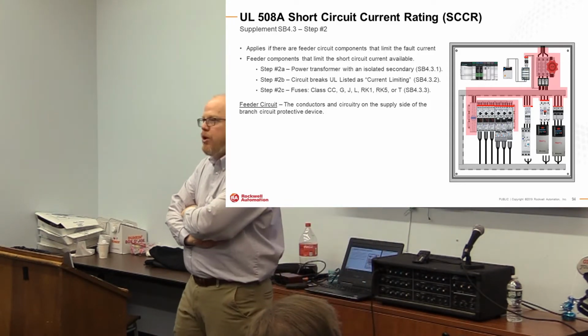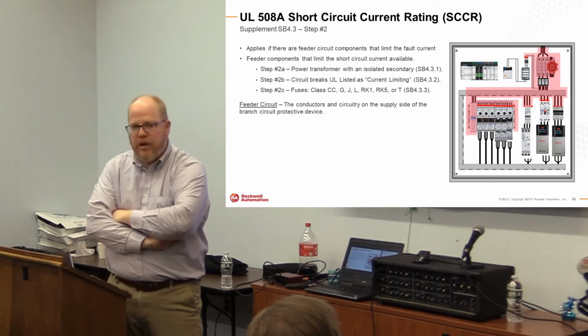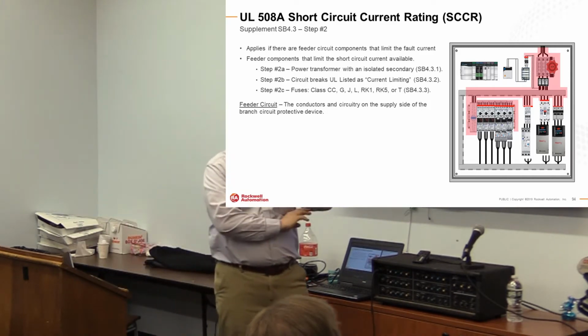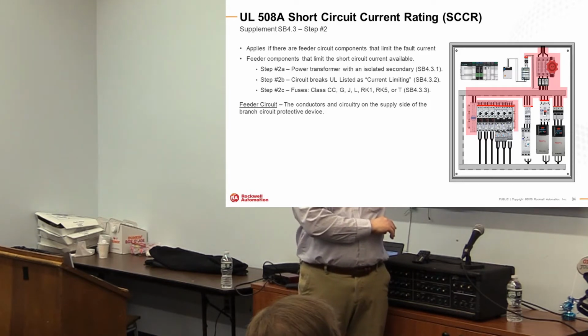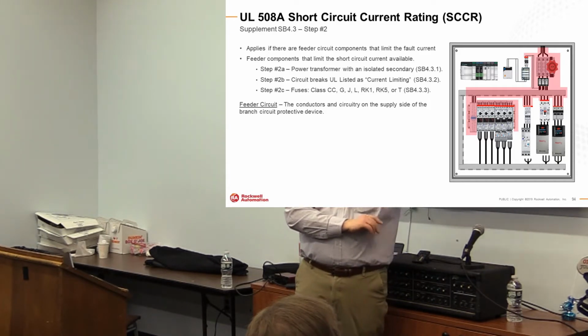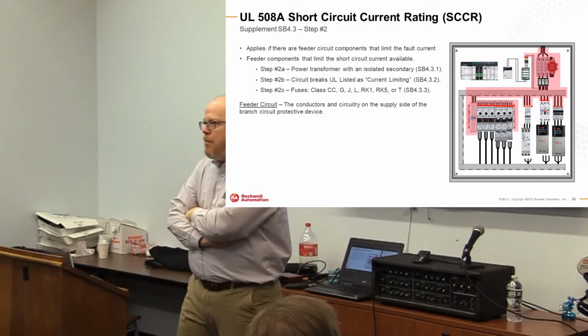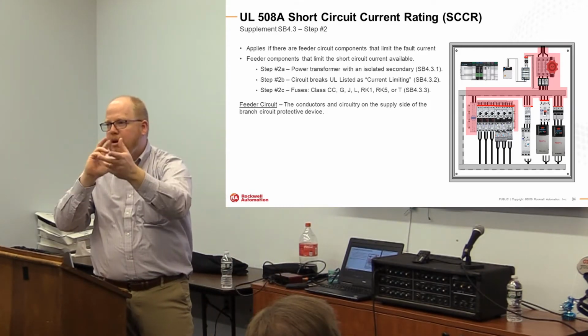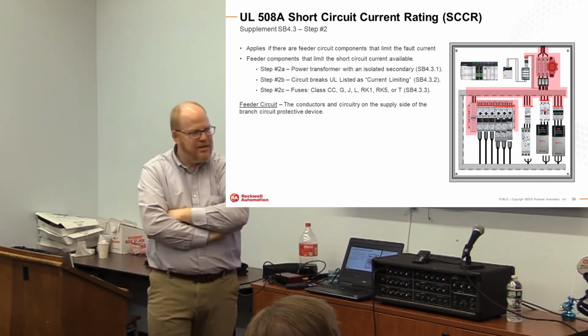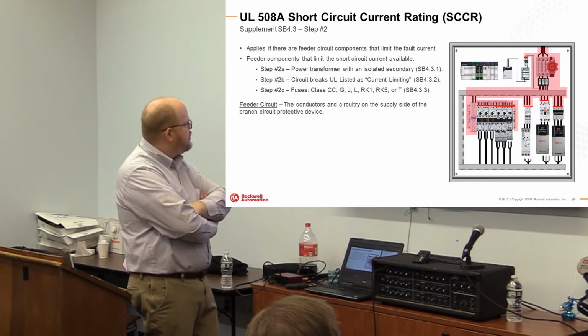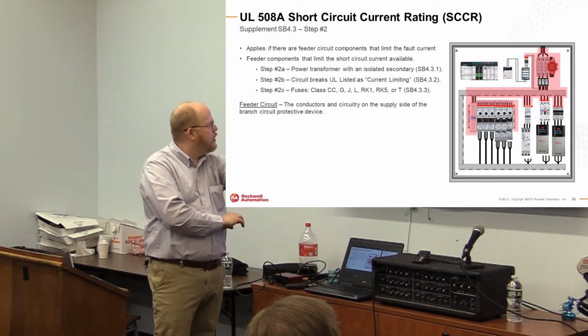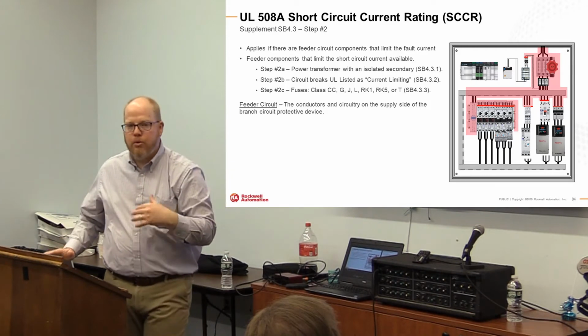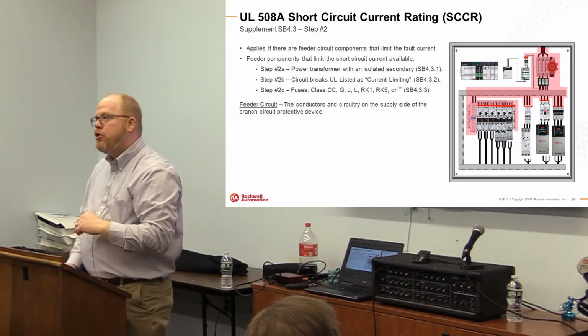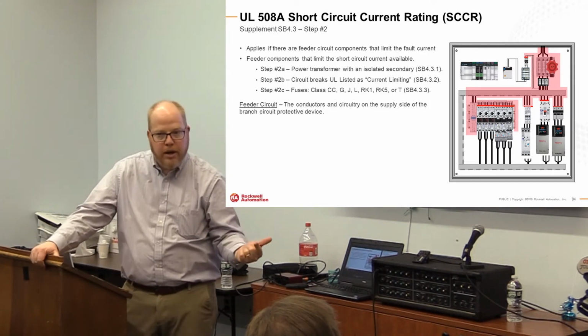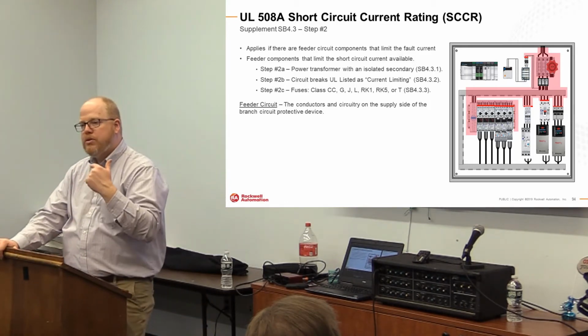So what we do is we go through step 1 for each branch, right? So we've got to know the SCCR. If it's a combination rating, it's simple, right? Boom, boom, boom. That's why a lot of times mixing and matching competitive products sometimes doesn't result in a simple solution. But you'll see here there are 3 ways to do current limiting. There's current limiting through a power transformer, there's current limiting through the use of a current limiting breaker, and there's current limiting through the use of fuses.